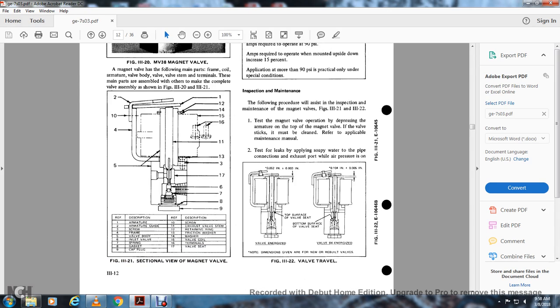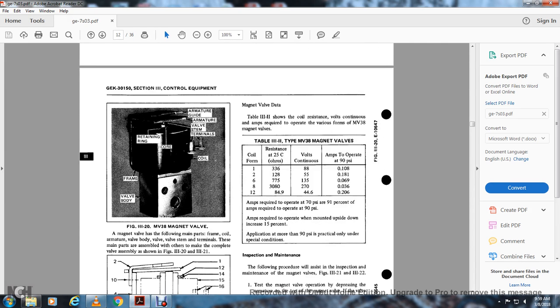Figure 321, sectional view of a magnetic valve. 1 is the armature, 2 is the armature guide, 3 the screw for the frame, 5 the valve body, 6 the inlet valve, 7 the spring, 8 the gasket, 9 the cap plug, 10 the screw, 11 the exhaust valve stem, 12 the retaining ring, 13 the friction washer, 14 the washer, 15 the valve coil, 16 terminal, 17 valve seat. Magnetic valve table 3-2 shows the coil resistance, volts continuous, and the amps required to operate the various forms of the MV38 magnet valve.